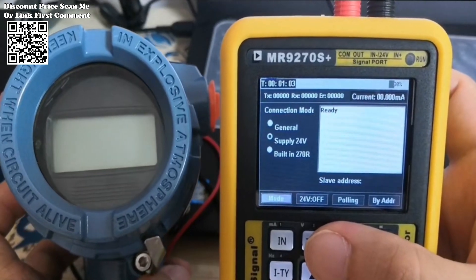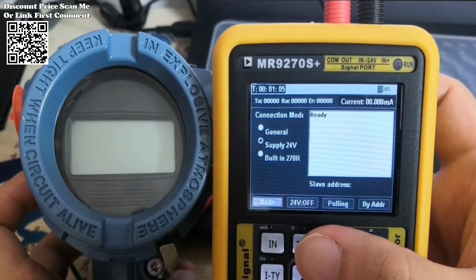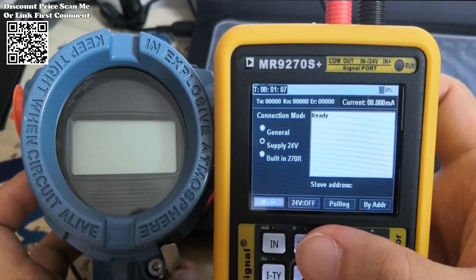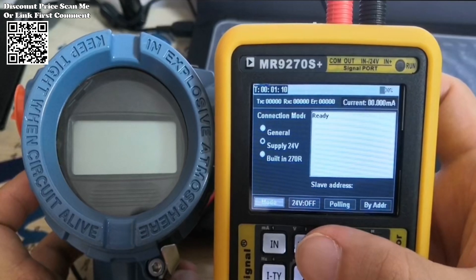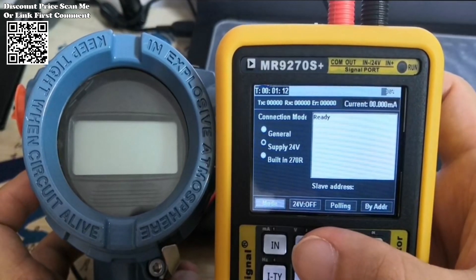That is, 4 milliampere corresponds to 0, 12 milliampere corresponds to 50, and 20 milliampere corresponds to 100. This range can be modified through parameters.